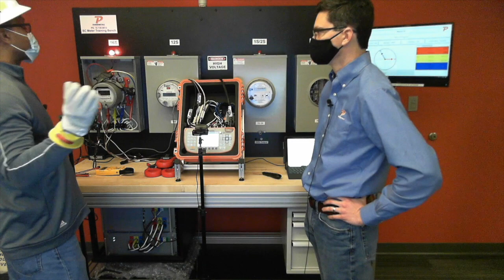So if I was going to do a demand test, let me go back to that. Why is it important, let's say I'm out there and the meter is programmed for 15 minutes, but I run a 5-minute demand test? Well, you get in there and you turn it in, well, the meter's good. What did it actually do? Compare apples to apples. Run it for 15 minutes and see what it does. I've done the 5 minutes, but to prove a point, you run it 15 minutes, the way the meter's calculated. If it's calculated 30 minutes, do it 30 minutes. I'm not saying sit in the truck. Stay with your meter and make sure it works.